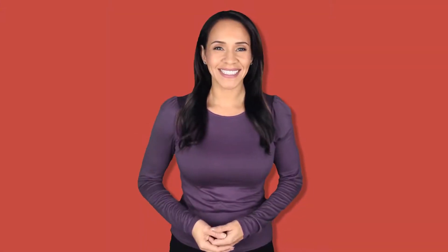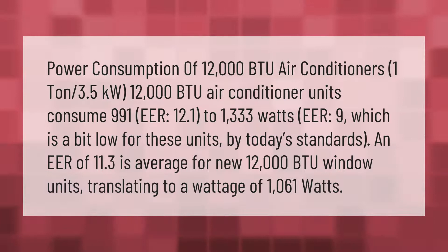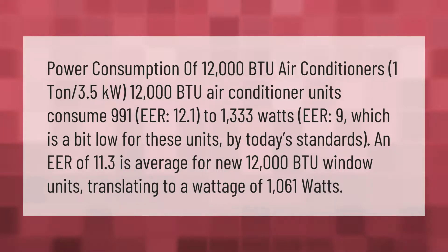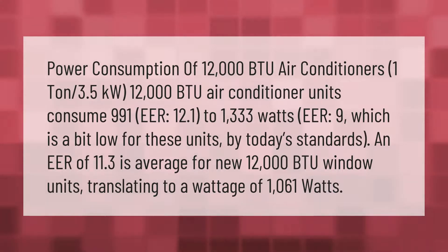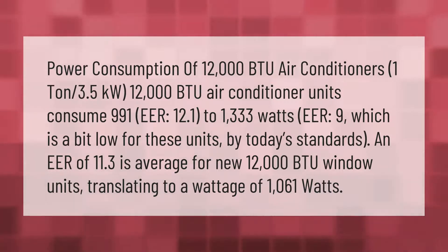Power consumption of 12,000 BTU air conditioners (one ton): at 3.5 kilowatts, 12,000 BTU air conditioner units consume between 991 watts (EER 12.1) and 1,333 watts (EER 9). An EER of 9 is a bit low by today's standards. An EER of 11.3 is average for new 12,000 BTU window units, translating to a wattage of 1,061 watts.